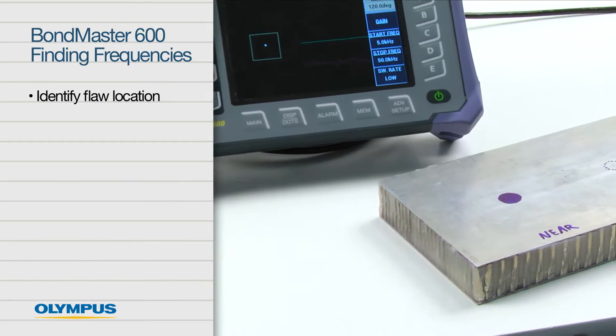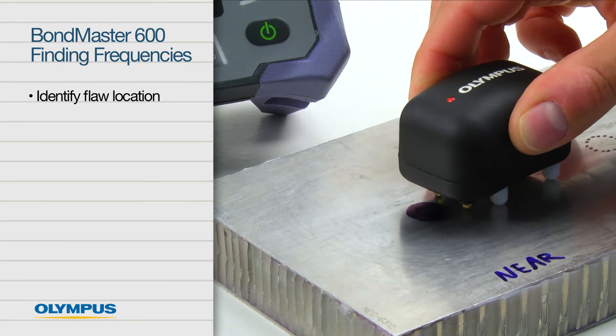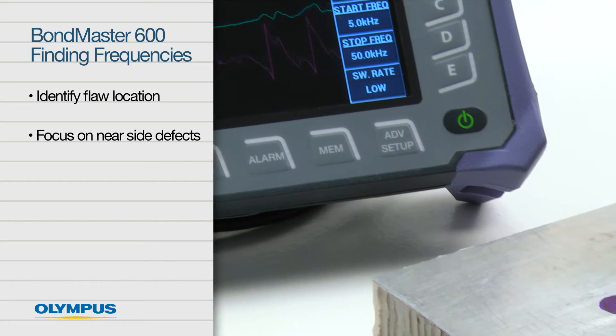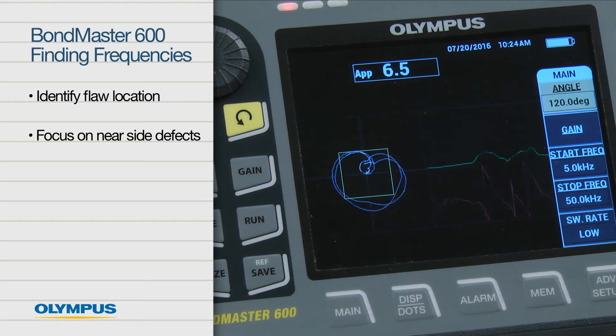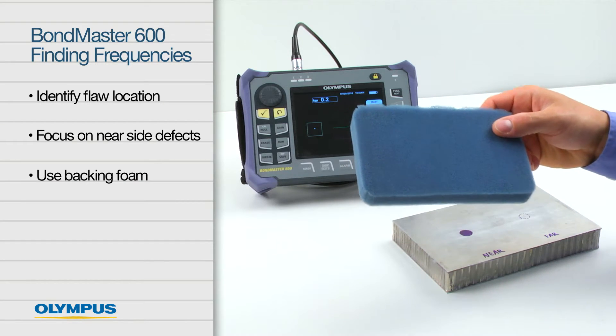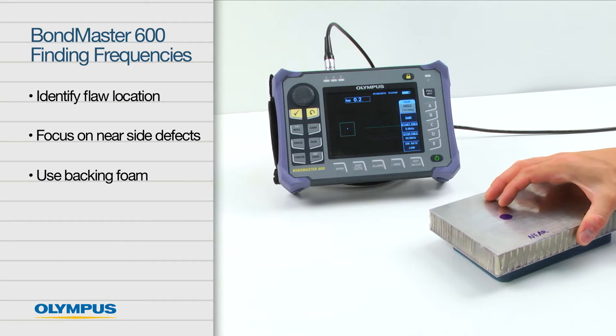Start by properly identifying the flaw location. Not doing so may result in confusion and possible errors. Focus on near side defects. Finding the proper frequency for near side disbonds will often result in the detection of far side disbonds. When possible, use a backing foam to reduce the effect of partial contact with the working table.